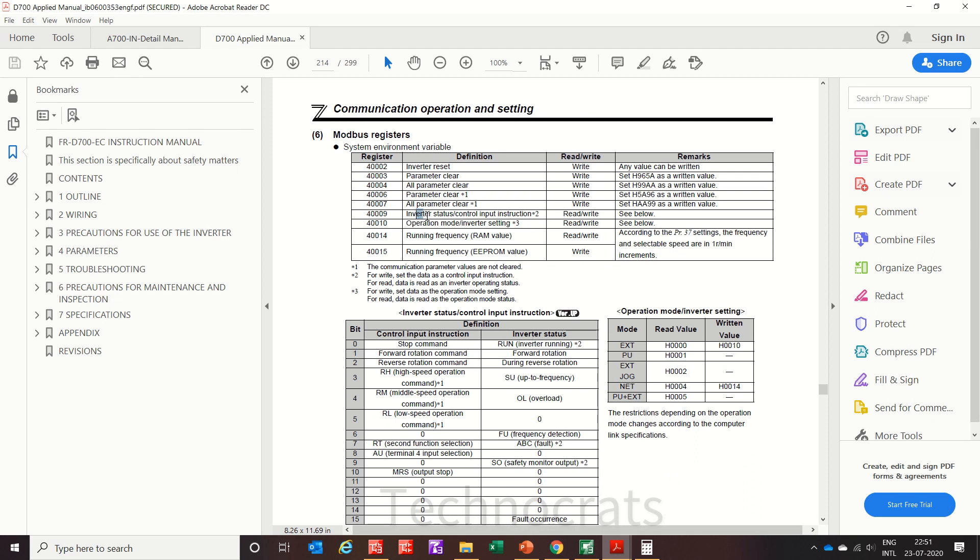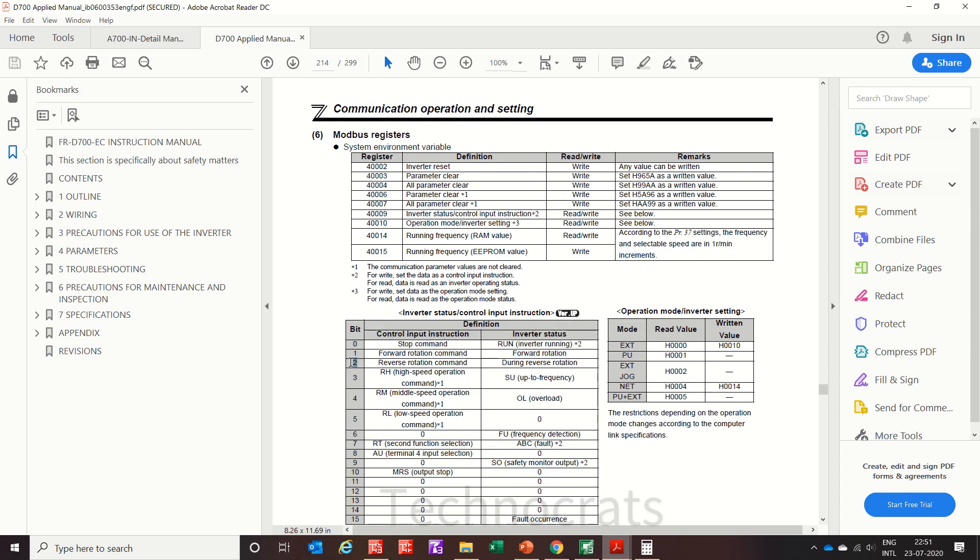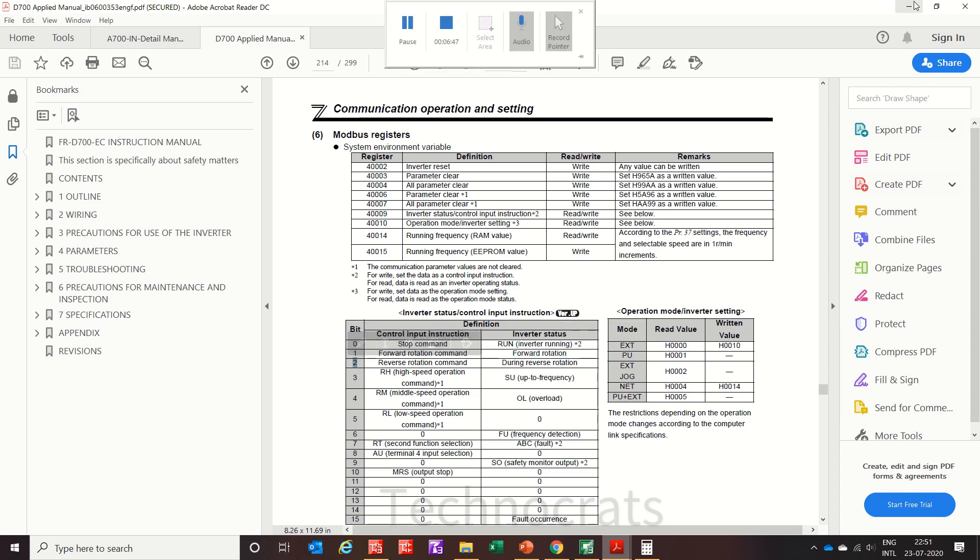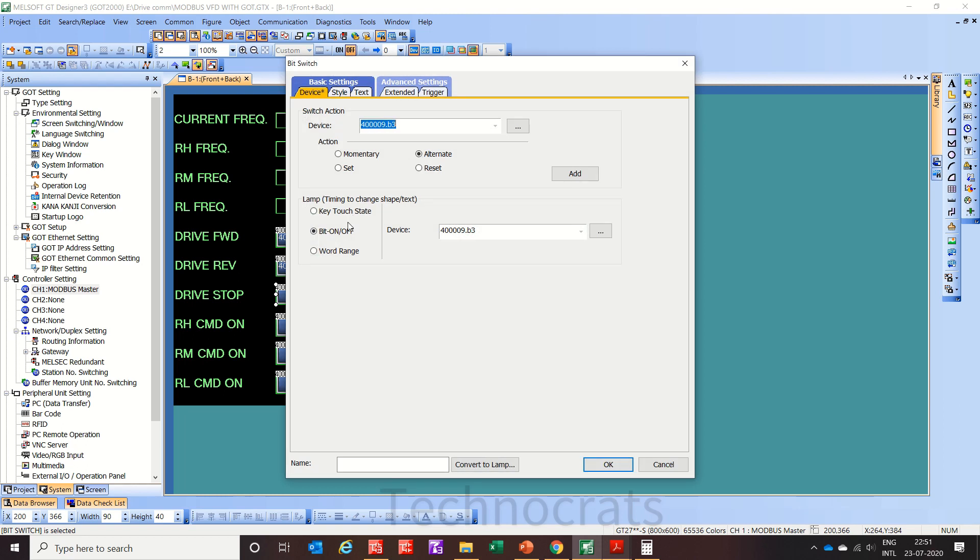So here in the manual you can see the inverter status and control input instruction. Instruction, see your forward rotation is bit number 1, reverse is bit number 2. Now this forward and reverse is okay. Now drive stop is bit number 0.